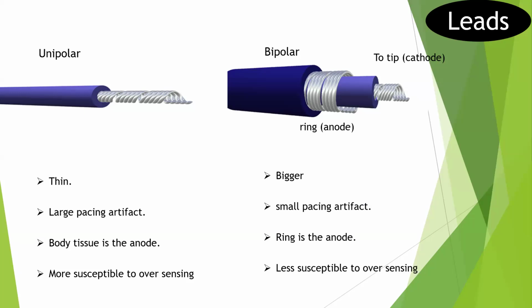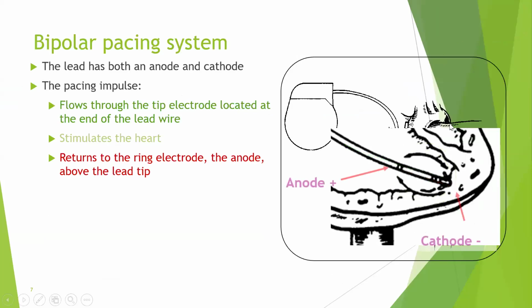It has a small pacing artifact because the stimulus is basically from the tip to the ring, which is a short distance. In addition, it is less susceptible to the environment because all the sensing and capturing happen inside the myocardium, not like the unipolar lead. So you can clearly see now the depolarization wavefront going from the tip to the myocardium, returning back to the ring of the electrode.